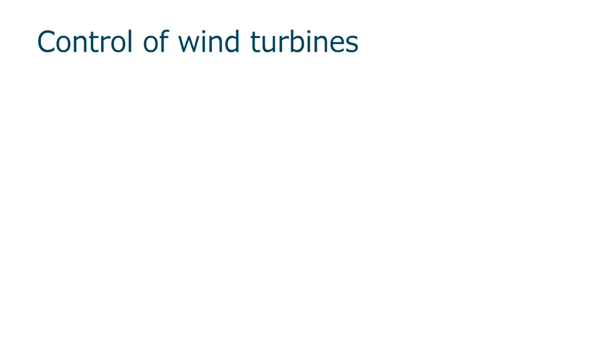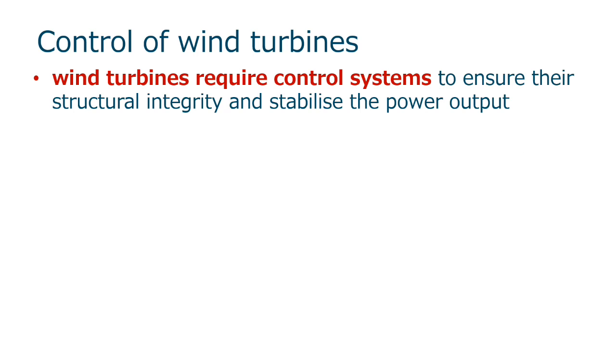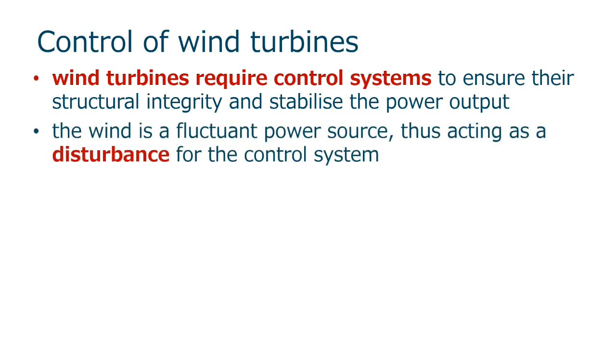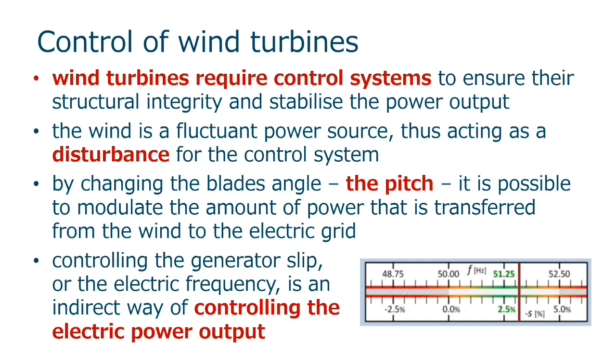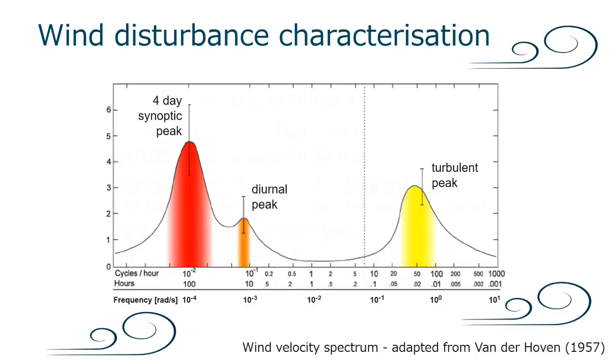Some considerations regarding the control of wind turbines. Wind turbines require control systems to ensure their structural integrity, and stabilize the power output. The wind is a fluctuating power source, thus acting as a disturbance for the control system. By changing the blade's angle, the pitch, it is possible to modulate the amount of power that is transferred from the wind to the electric grid. Controlling the generator slip, or the electric frequency, is an indirect way of controlling the electric power output. This plot provides the same information regarding the expected spectrum for the wind disturbances. That will be used to set the disturbance rejection bandwidth on 0.1 radians per second.